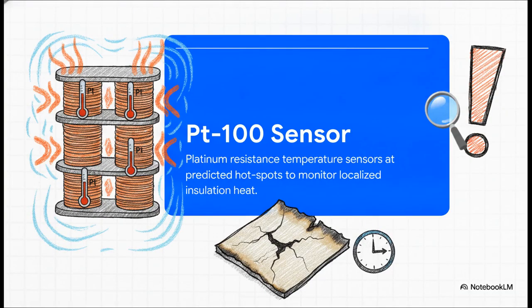And that's exactly where the PT100 sensor comes in. These are platinum resistance temperature sensors. The brilliant thing here is that they sit directly at predicted hotspot locations deep inside the winding, not just bobbing around in the bulk oil. It's an absolutely crucial design choice because it's that localized hotspot temperature, not the average oil temp, that actually cooks and ages the insulation over time.